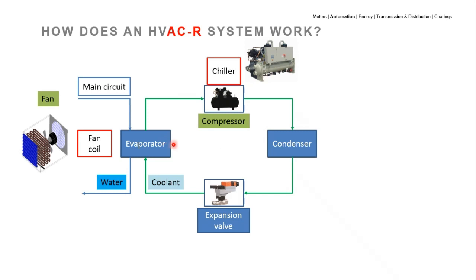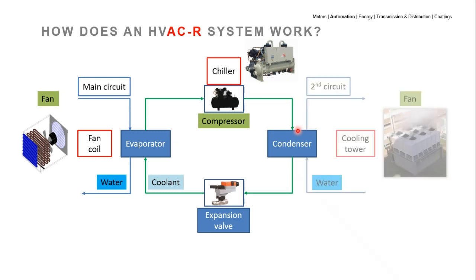On the interior side, water exchanges heat with the coolant through the evaporator, then goes through cooling coils where a fan blows cool air to offices, hospital rooms, and so on. This is the main circuit. The coolant, after passing through the evaporator and exchanging heat with the water, gets hotter and moves through the circuit to the condenser. On the secondary circuit on the right side, you cool down the coolant using cool water that goes through a cooling tower. Fans help cool the water temperature down, and then it circulates through the condenser to exchange heat with the coolant.